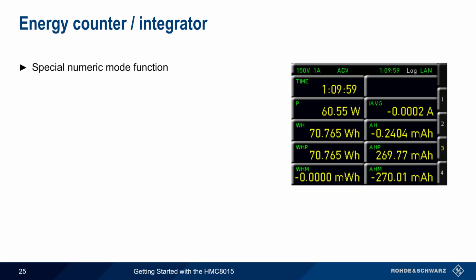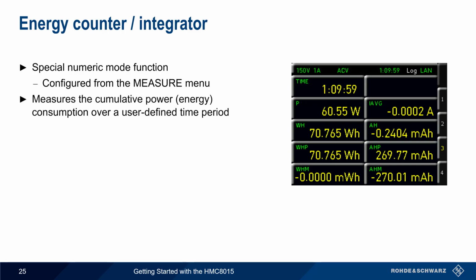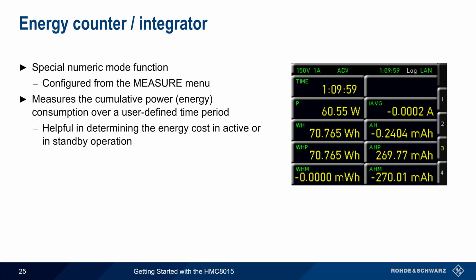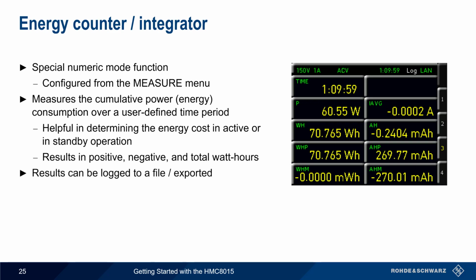The energy counter or integrator is a special numeric mode configured from the Measure menu, and this calculates and displays the cumulative power or energy consumption of a DUT over time. This can be helpful in determining the energy cost of a device in both active and in standby operation. The HMC calculates the energy consumption over time and reports the results in positive, negative, and total watt-hours, updated in real time. These results can also be logged to a file and exported for documentation or for further analysis.